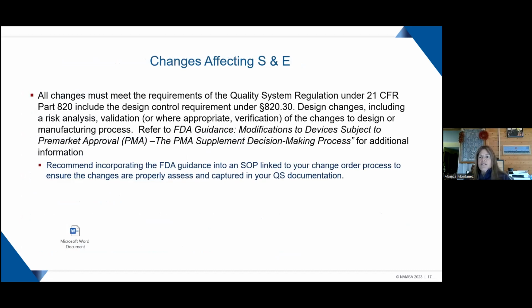So now my favorite subject, changes affecting safety and effectiveness, which is really the key to determining the submission type. All changes must meet the requirements of the quality system regulation under 21 CFR Part 820, including design controls, design changes, including a risk analysis, validation, and where appropriate, verification of the changes to design or the manufacturing process. I highly recommend referring to FDA's guidance document, Modifications to Devices Subject to Premarket Approval: The PMA Supplement Decision-Making Process, for additional information. It's highly recommended from me and others to incorporate that FDA guidance document into an SOP that's linked to your change order process, or whatever you call it.